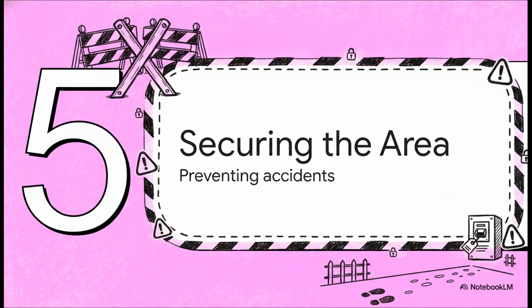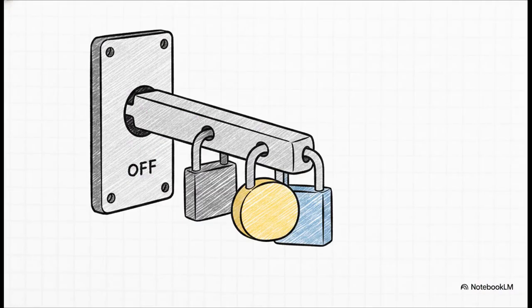Section 5. Securing the area and preventing accidents. So, the crucial point is that once you've proven the power is dead, you have to ensure nobody else accidentally reverses the safe environment you've just methodically created. If you don't have sole, effective control of the isolation device at all times, it must be physically locked off. You need built-in locks or lockout jaws. And importantly, every individual worker on the job applies their own personal lock. It also needs to be sturdy enough to withstand vibration or someone inadvertently bumping into it.